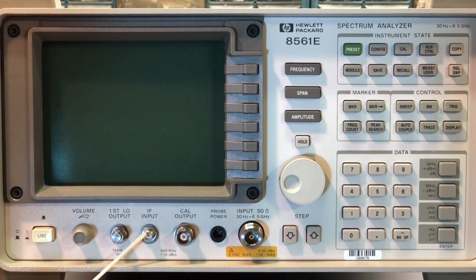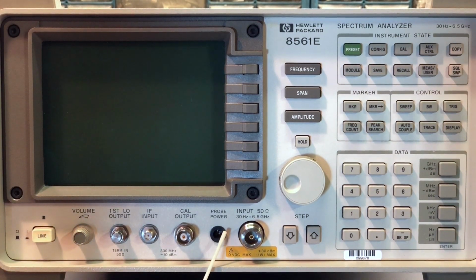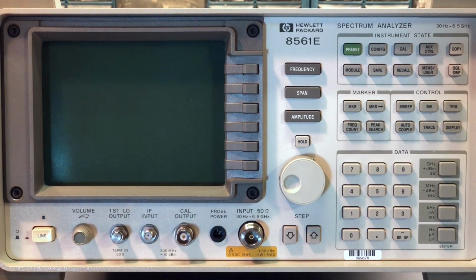IF input, or intermediate frequency input. Right here, this calibration output is a 300 megahertz signal used in calibrating the instrument. You can see it says 300 megahertz at minus 10 dBm. Probe power for active probes. There's 3 little pins in here for the connector, and I do have some active probes, so that's very handy. It's a common type of connector that was used on Hewlett-Packard and other models that they made, so you can use the same probe between different models. There's actually 2 different DC voltages that are produced in here, and then there's a ground connection.